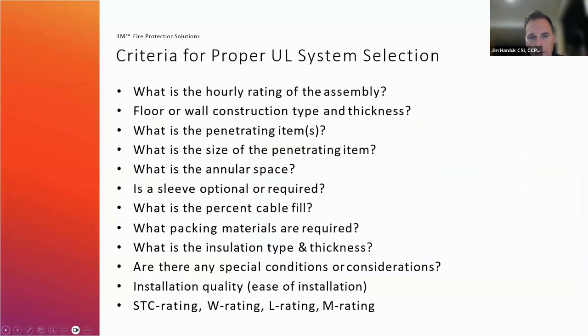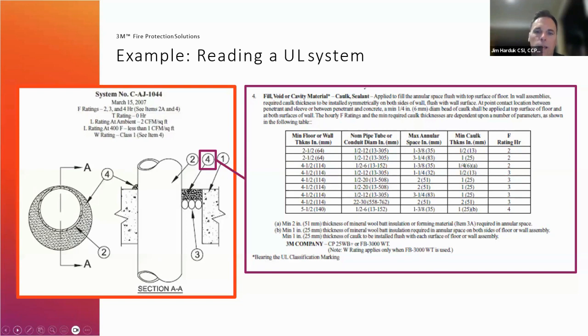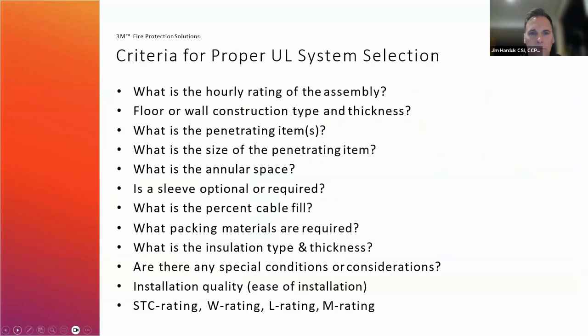And then at the very bottom, back up one slide. Yeah, at the very bottom, it'll tell you what products can be used to fire stop that application. And it'll tell you the required thickness if you're dealing with a spray or if you're dealing with a sealant. In this case, we're dealing with a sealant. And you may find that there might be multiple products that can be used for one system. And I'll touch on that in a few slides here. Next slide, please.